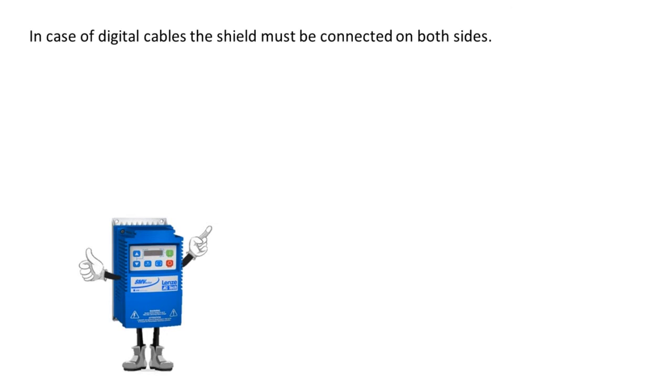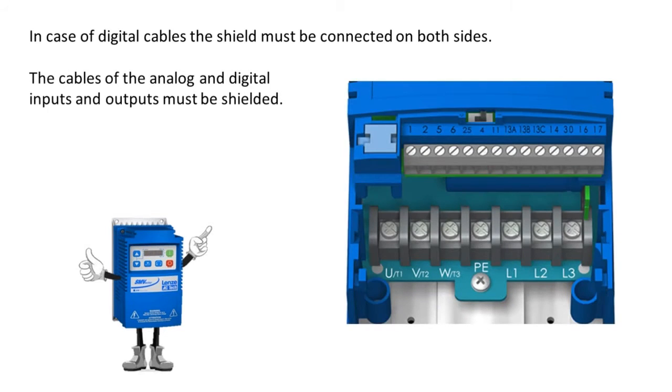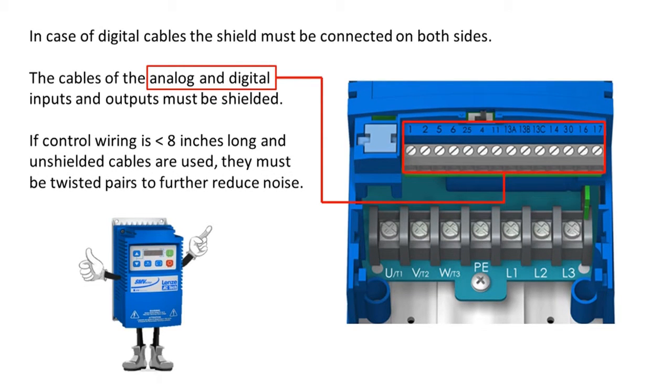The cables for the digital connections must have their shield connected on both sides. The cables of the analog and digital inputs and outputs must be shielded cable. If control wiring is less than eight inches long and unshielded cables are used, they must be used with twisted pairs to further reduce noise.